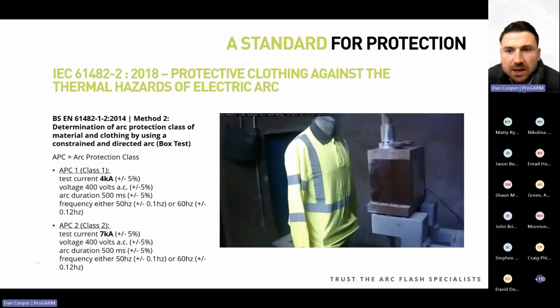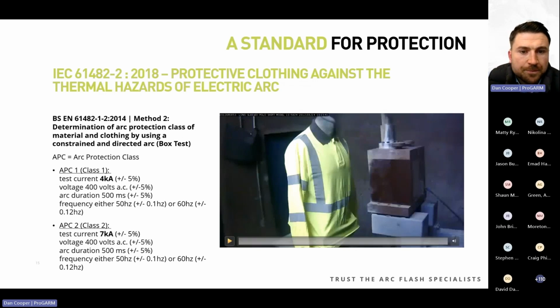Now, the box test is another method predominantly specified in Europe, and two results are given from this method: arc protection class 1 with a test current of 4 kA and arc protection class 2 with a test current of 7 kA. This test is a bit more of a constrained and directed arc test, as shown in this short video.